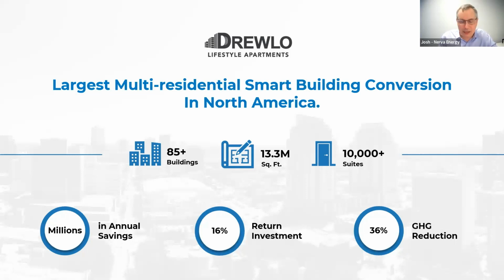But on these existing buildings, we have thousands of MURBs that need one or two, in most cases, heat recovery units on the roof. At that point we can capture at least 75%, if not 90%, of the heating and cooling energy we're pulling out of the suites and pass that back into the makeup air stream. It's not free—we're still losing a bit of percentage—but we can heat and cool that makeup air for very low cost and very low carbon emissions compared to what we were doing before.